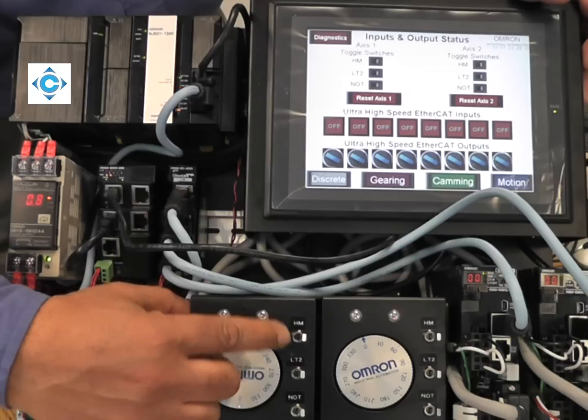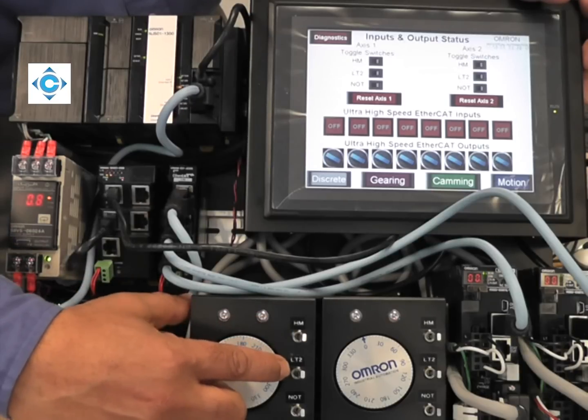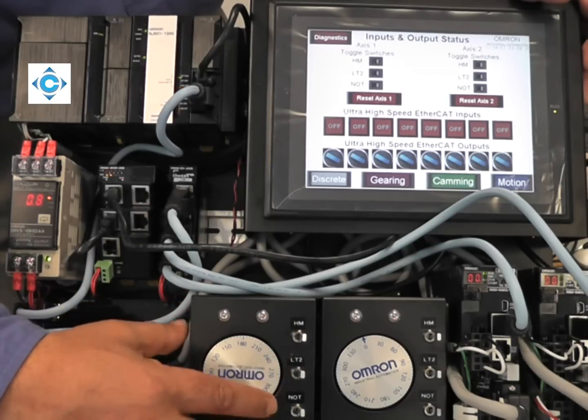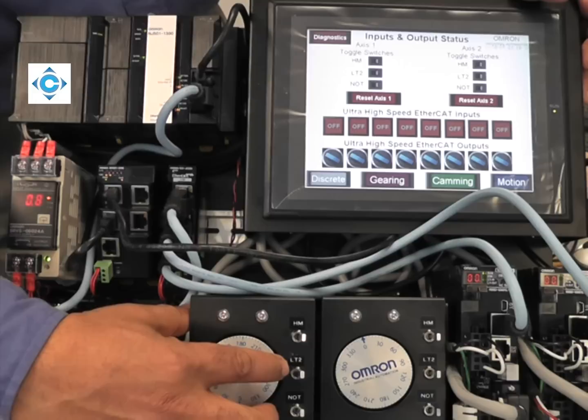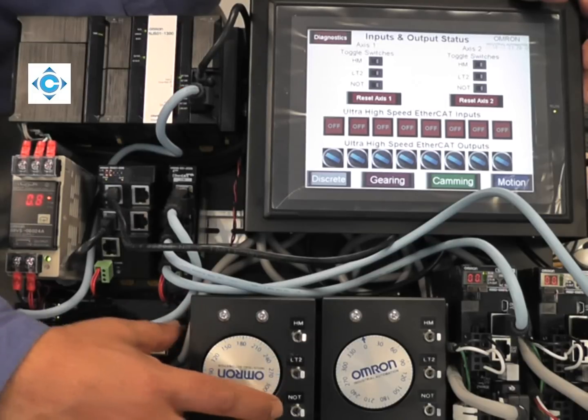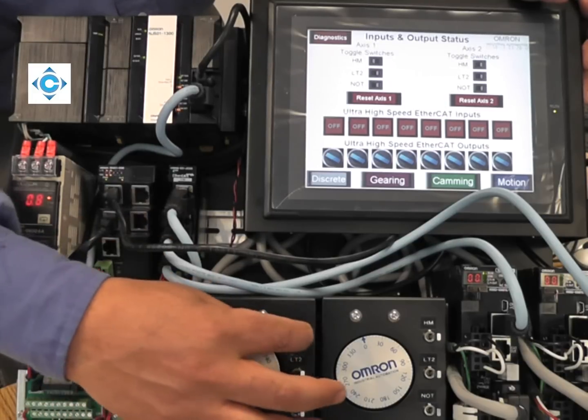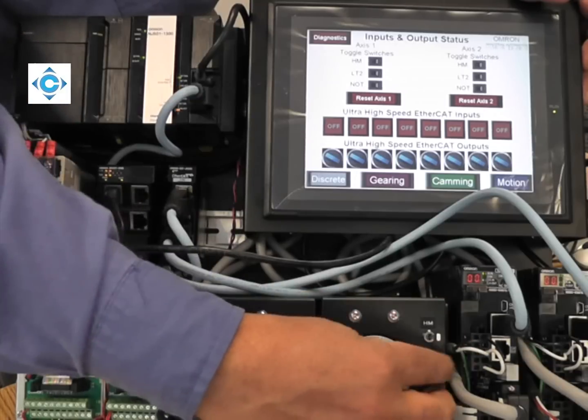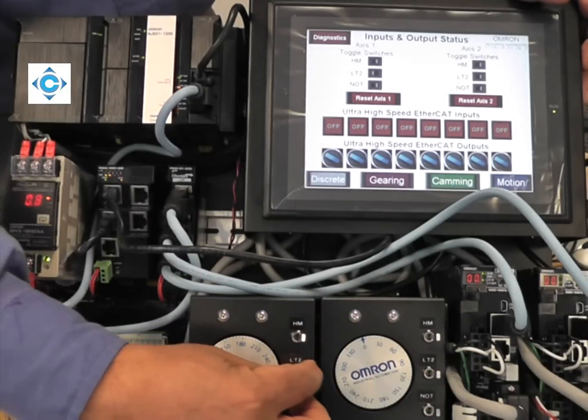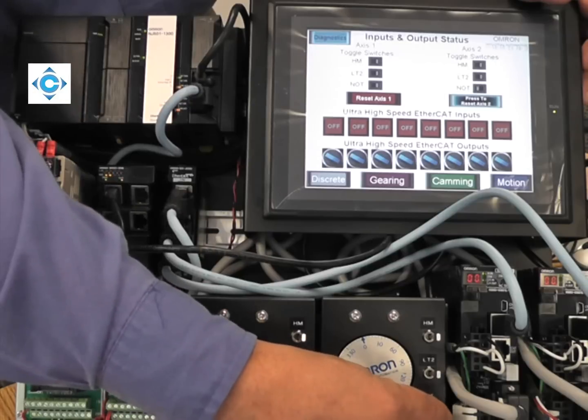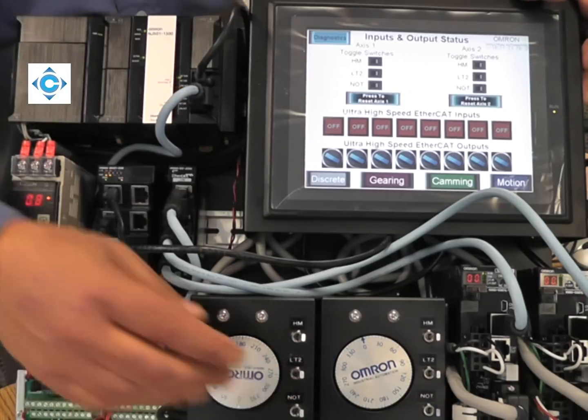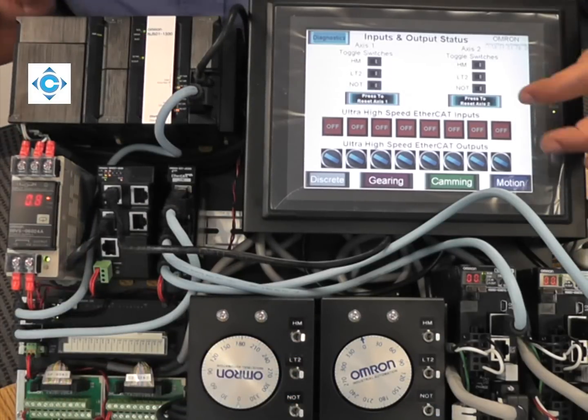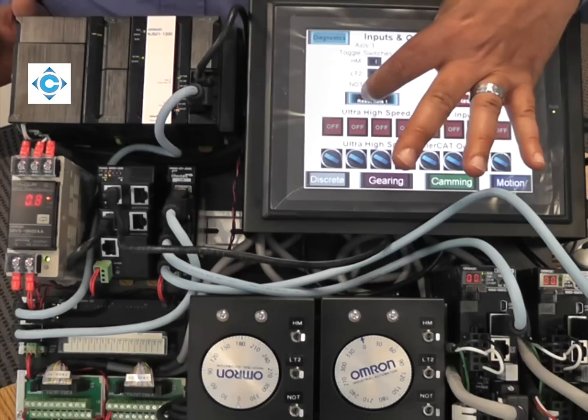Each G5 has eight inputs and three outputs. We just wired three of the inputs: the home, limit switch, the second limit switch which is our registration, and the negative over-travel. If you just toggle one, you will see it changing on the screen. If you activate the negative over-travel, it's configured in the drive to cause a fault.